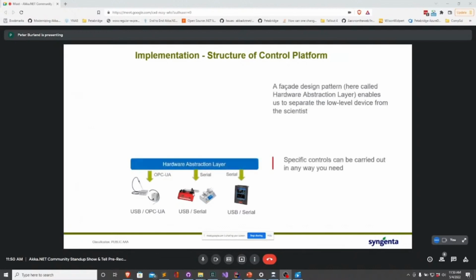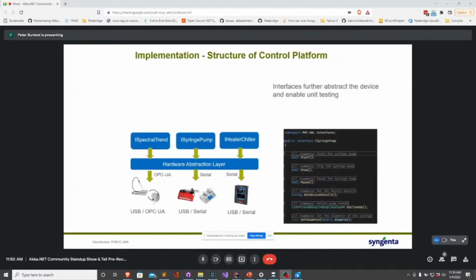So the hardware abstraction is nothing too sophisticated. It boils down to a load of interfaces that sit at a level of abstraction over the real physical device. I didn't want to show too much code, but this is a snippet of the syringe pump interface. We're saying I don't care which syringe pump I've added, as long as it can start, stop, pause, get the data out and set the syringe diameter. These are common behaviors of all syringe pumps. That's a simple way of almost getting rid of the actual device as we build on the actor framework.